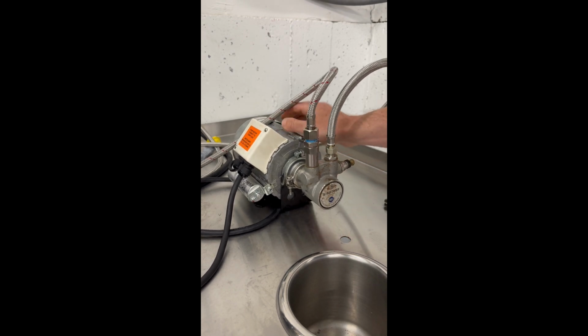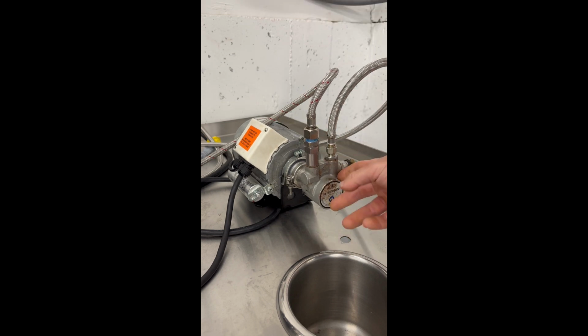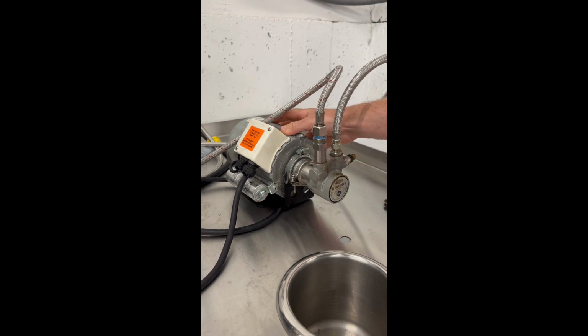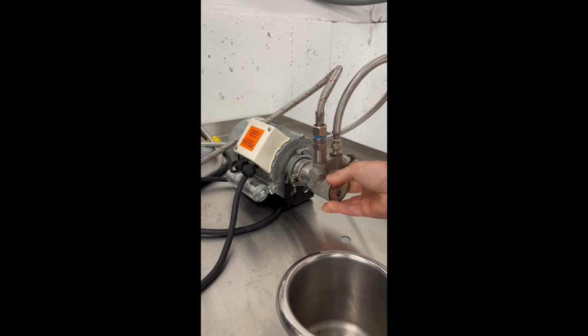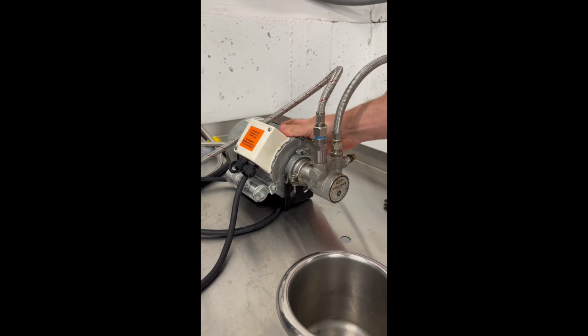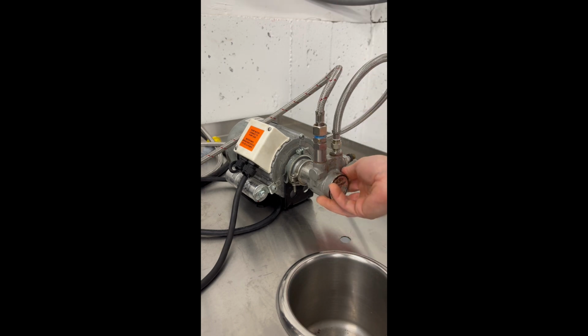The other thing, if you feel this vibrating, but you don't really have any pressure, then this pump head, there's 2 separate parts. This is the motor, and this is the actual pump part of it. So if you feel the motor going, but you don't have any pressure, or you don't have 9 bars of pressure at least, it's very possible that your pump head or your pump itself has failed and needs to be replaced. They do get stuck, they do fail. It's not that crazy of a thing.